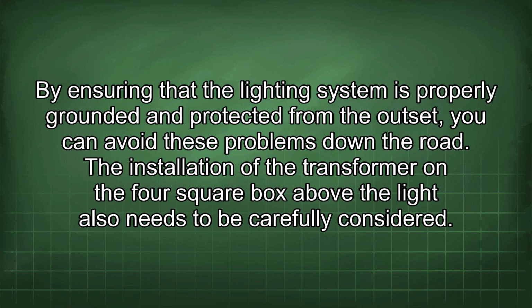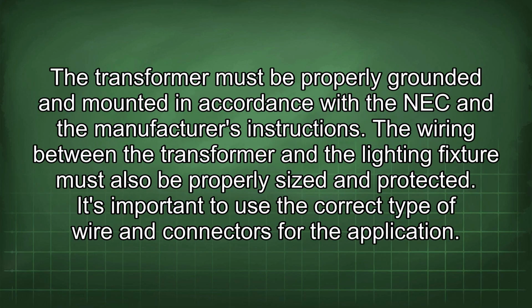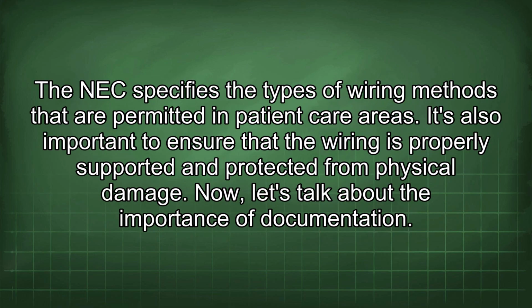The installation of the transformer on the 4 square box above the light also needs to be carefully considered. The transformer must be properly grounded and mounted in accordance with the NEC and the manufacturer's instructions. The wiring between the transformer and the lighting fixture must also be properly sized and protected. It's important to use the correct type of wire and connectors for the application. The NEC specifies the types of wiring methods that are permitted in patient care areas. It's also important to ensure that the wiring is properly supported and protected from physical damage.